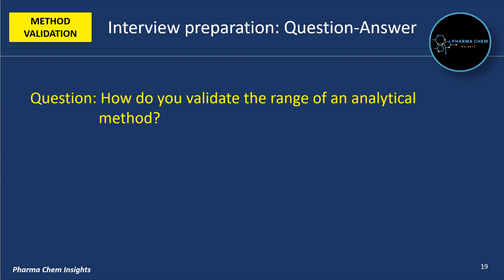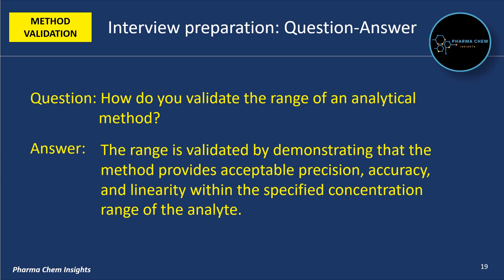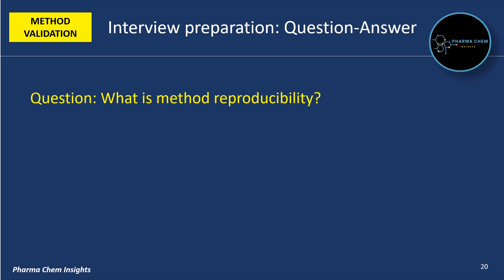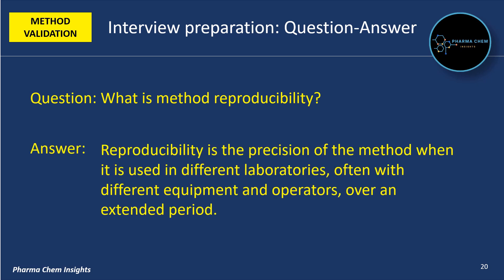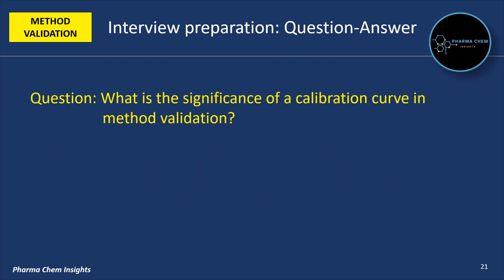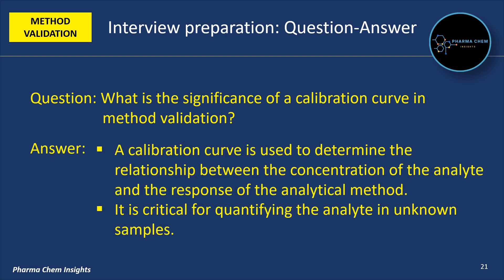Next question: how do you validate the range of an analytical method? The range is validated by demonstrating that the method provides acceptable precision, accuracy and linearity within the specified concentration range of the analyte. What is method reproducibility? Reproducibility is the precision of the method when it is used in different laboratories, often with different equipment and operators, over an extended period. Next question: what is the significance of a calibration curve in method validation? A calibration curve is used to determine the relationship between the concentration of the analyte and the response of the analytical method, and is critical for quantifying the analyte in unknown samples.